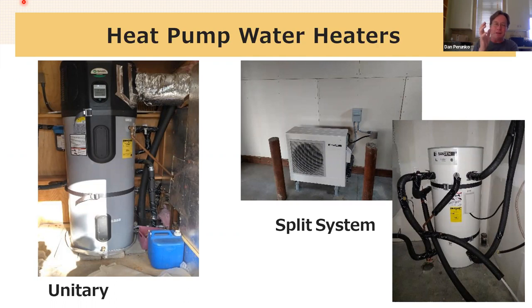Plumbers and contractors and pretty much everybody else like really sort of visually organized things, right? Like what looks really great in a mechanical room, rows of pipes, and then they all sort of turn, right? They maintain the same distance away from each other and they're super organized looking, usually not insulated. When we do that, there's a high degree of assembly skill in evidence on the part of the plumber who built it, right? Those are very good work. From the perspective of moving water and moving heat, it's a terrible way to do it. We have huge amounts of heat loss because the pipes are generally not insulated well. And every time we make a hard bend, we're creating resistance to water flow, so we're increasing pumping energy.